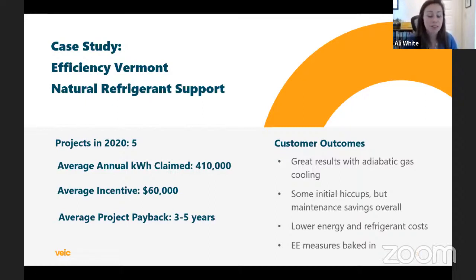The average savings we were able to claim was 410 megawatt hours annually over a baseline system. Sometimes that was a baseline CO2 system that did not have any added efficiency components. Sometimes it was a traditional 404A system. The average incentive that we were able to bring forth was $60,000, resulting in a payback of the incremental cost associated with the natural refrigerant system being between 3 to 5 years, which is within an acceptable rate for most organizations.